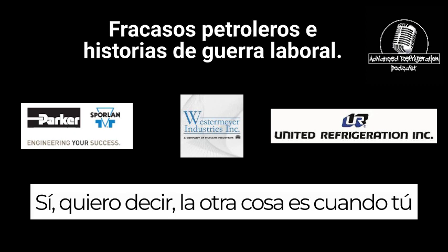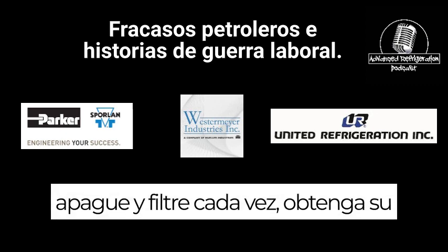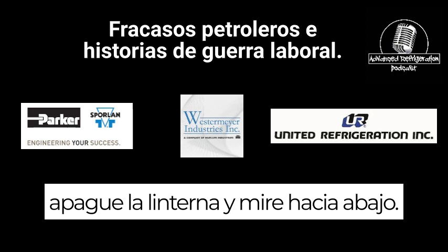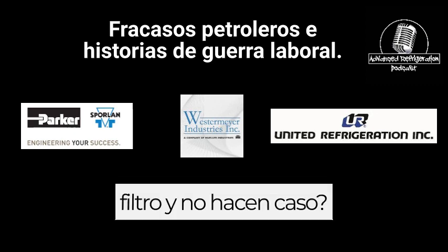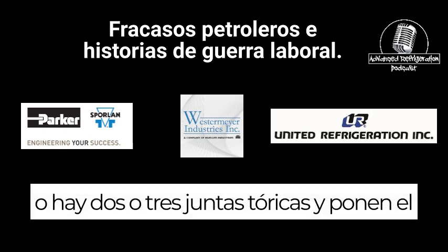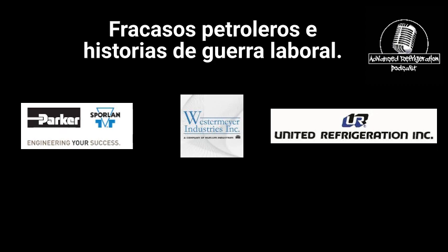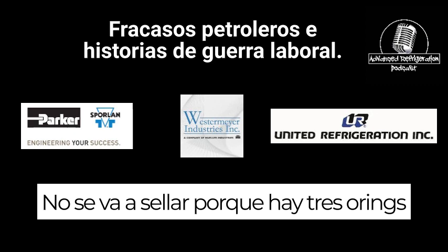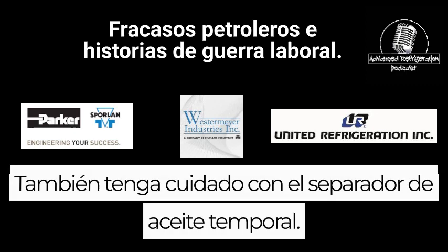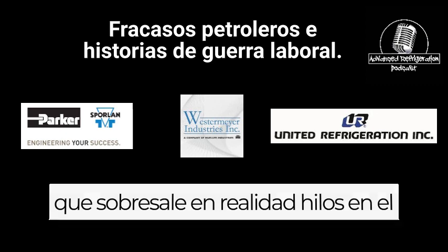Yeah. I mean, the other thing is when you are doing these filters, when you pull the lid off and take the filter apart, every single time get your flashlight out and look down there. I don't know how many times I've seen guys change the filter and they don't pay attention, and the O-ring's blown off, it's sitting on the base, or there's 2 or 3 O-rings on the base, and they stick the new filter right on top of them, and it's not going to seal because there's 3 O-rings at the bottom or 1 O-ring at the bottom.